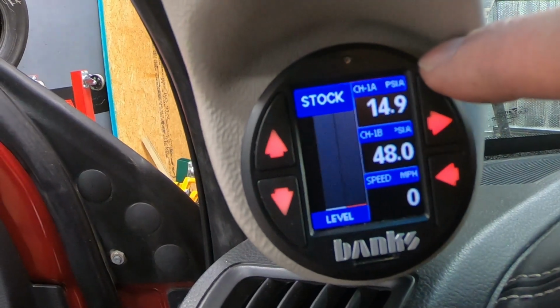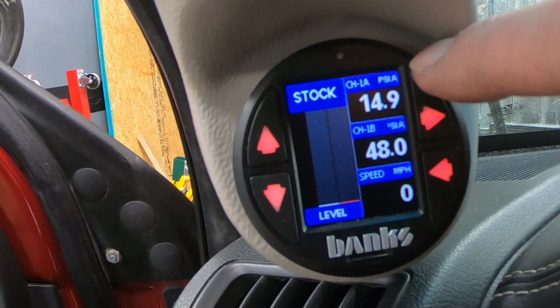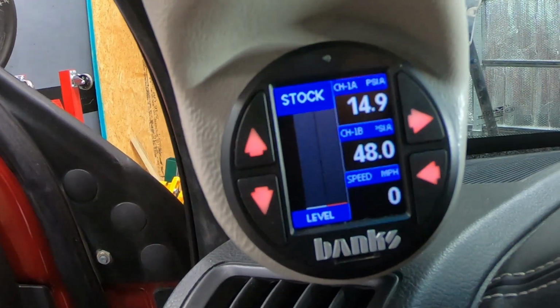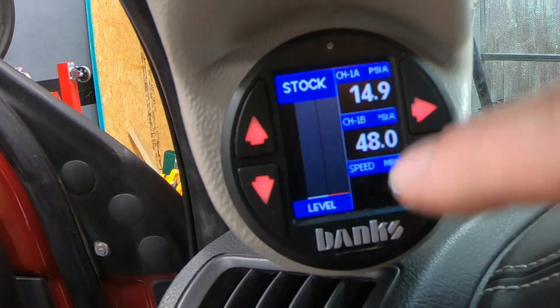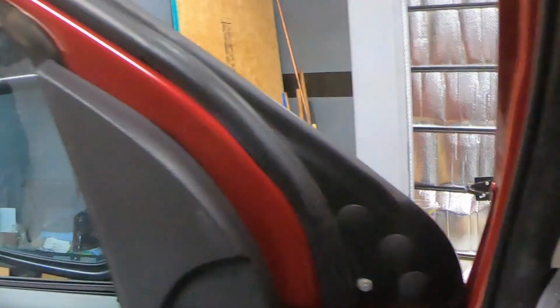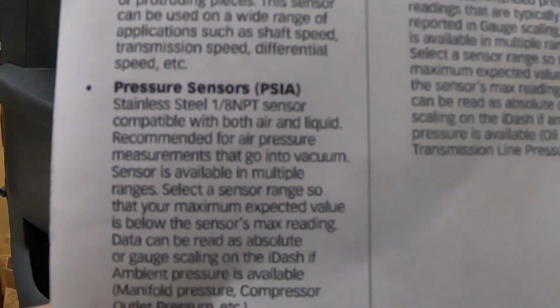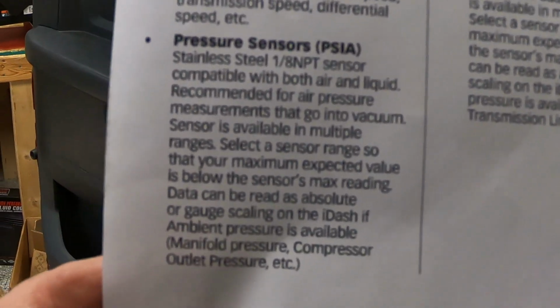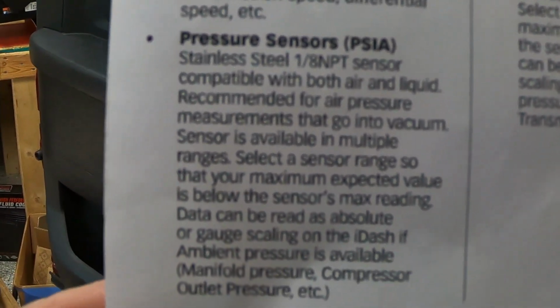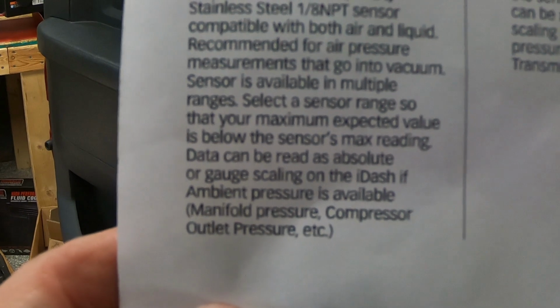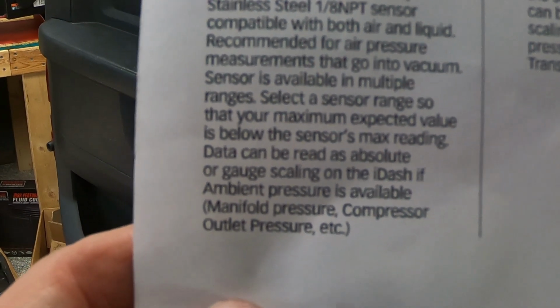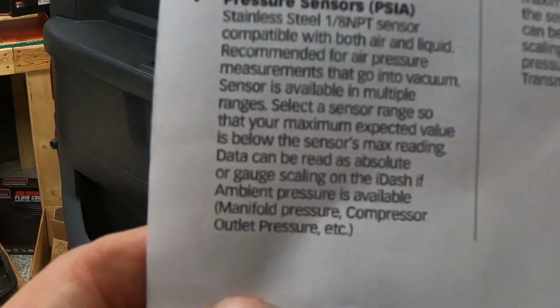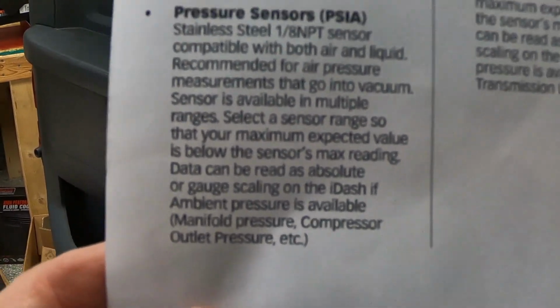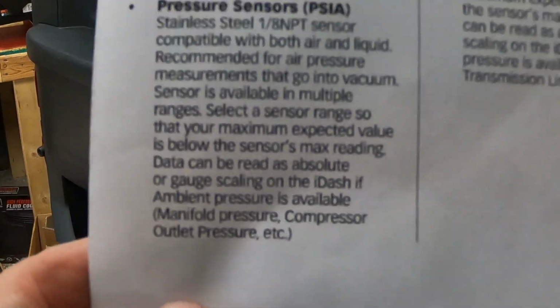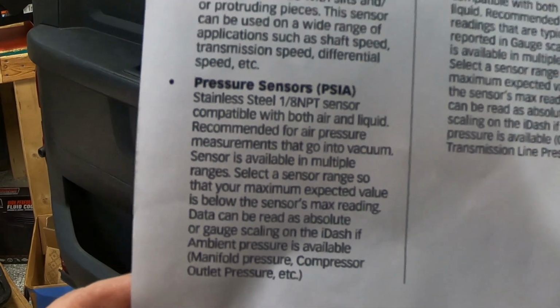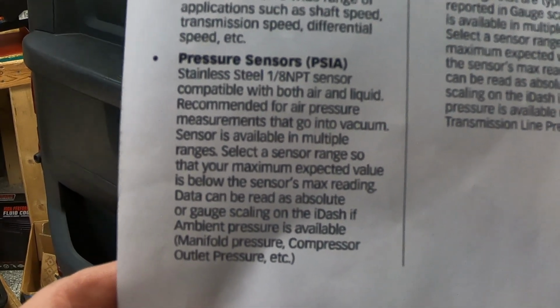So now this page comes back and resets. You see we have channel A, our fuel pressure, and channel B, our boost pressure. Now PSIA and PSIG are a little different between the two. This is a section from the 4-channel analog module's install manual, and it notes PSIA is compatible with both air and liquid, recommended for air pressure measurements going into vacuum, which is why I selected this, since that 0 to 15 sensor is potentially going to see manifold vacuum. So I ordered both sensors as PSIA.